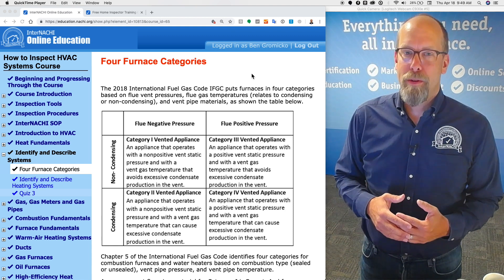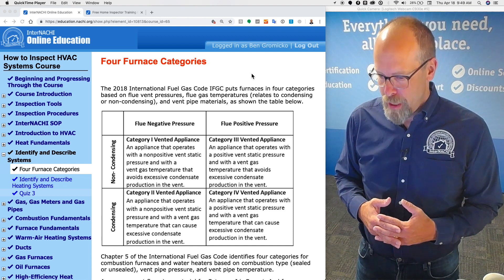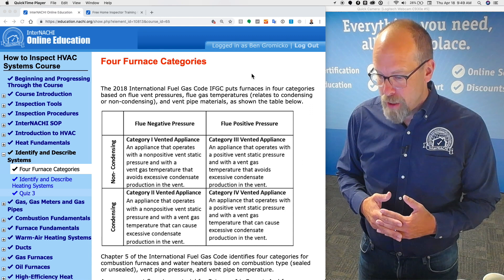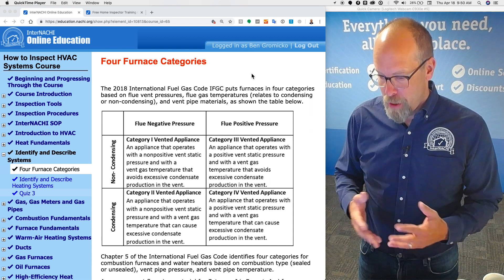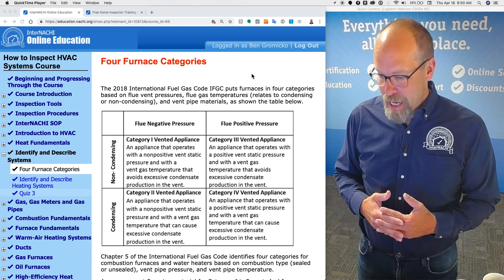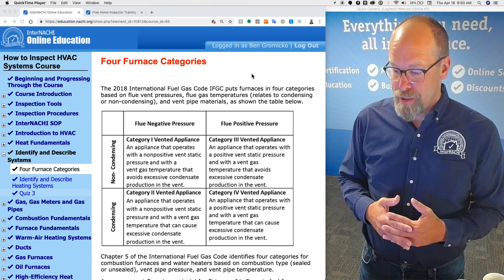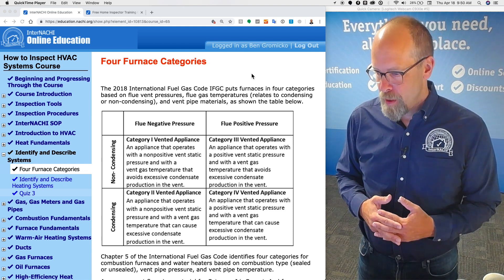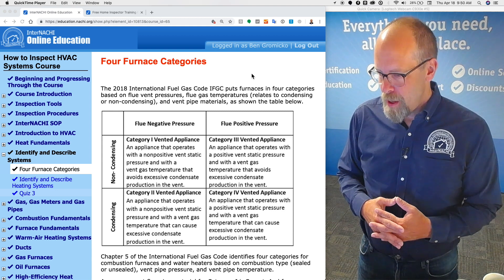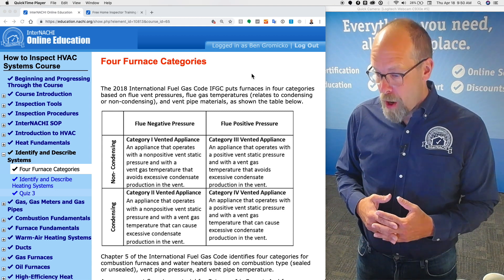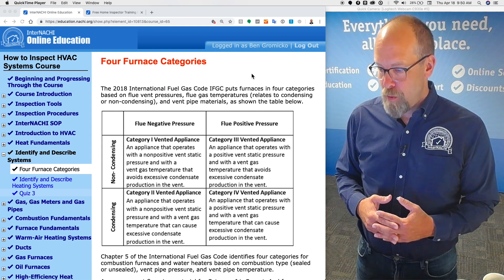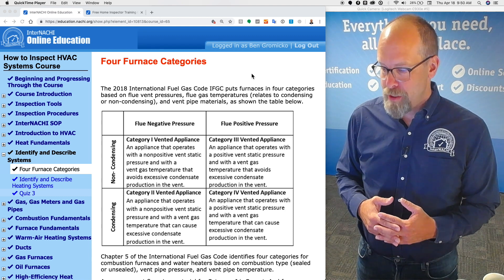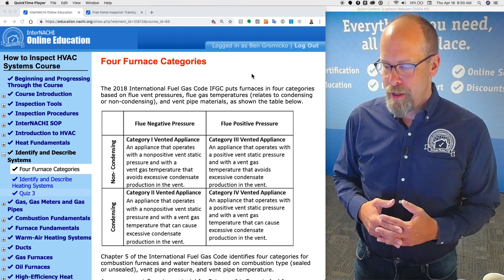Category two, not really common for residential, is an appliance that operates with a non-positive vent static pressure and with a vent gas temperature that can cause excessive condensate production in the vent. Category three, an appliance that operates with a positive vent static pressure and with a vent gas temperature that avoids excessive condensate production in the vent.